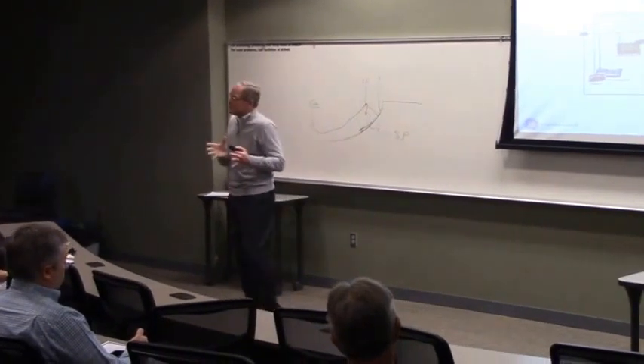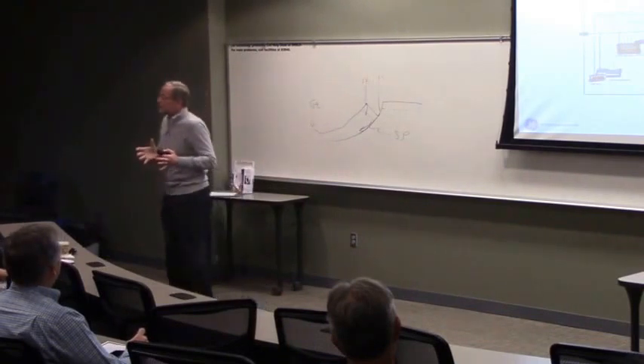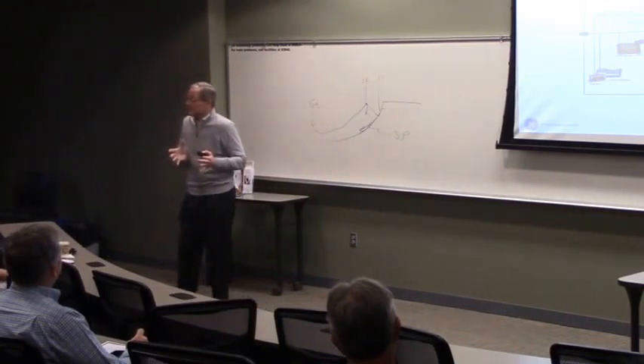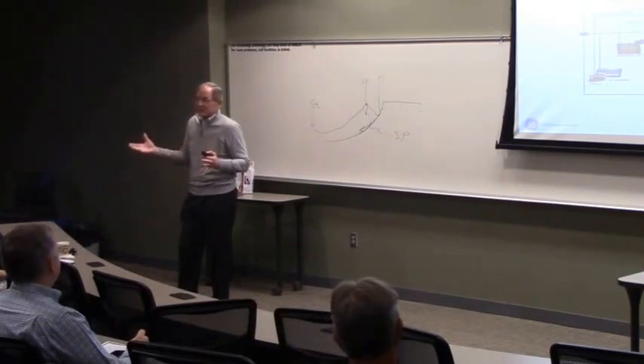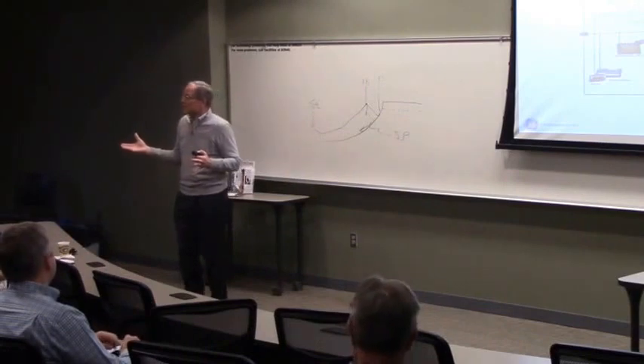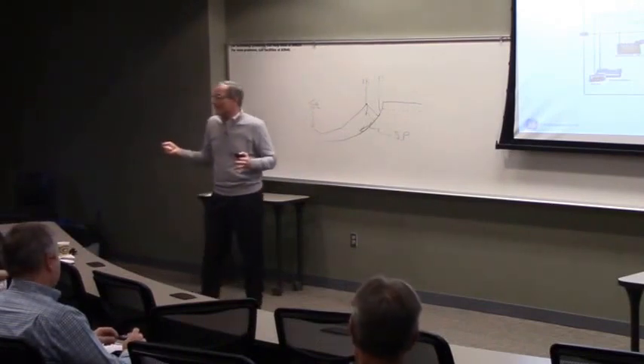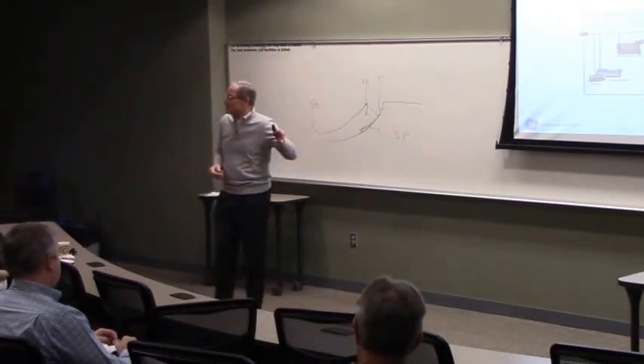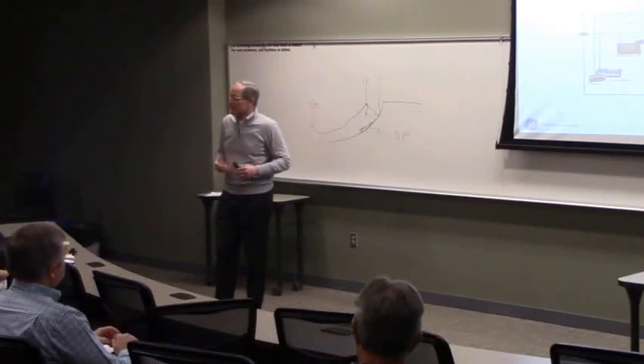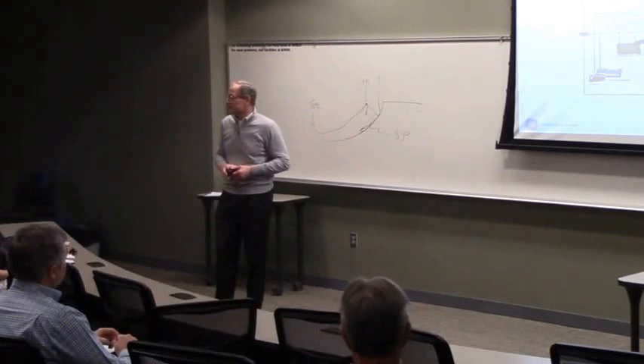What's in the substation? A tap changer on the transformer. We want to keep the voltage on the secondary side of the transformer constant. The low voltage network that feeds the customers, you want to keep that constant no matter how much the primary voltage fluctuates. This tap changer on this feeder was operating 5, 6, 7 times per day.